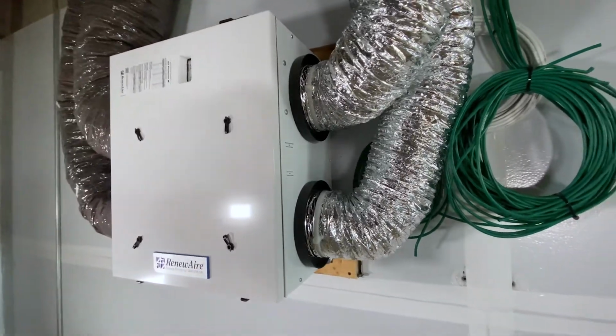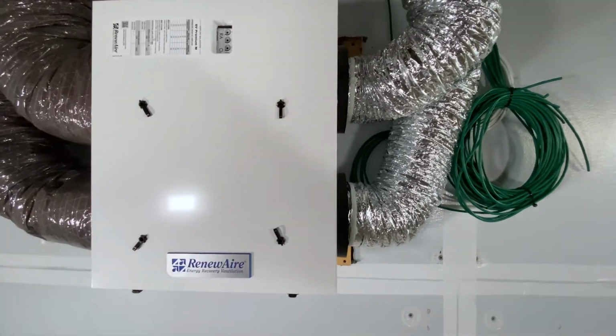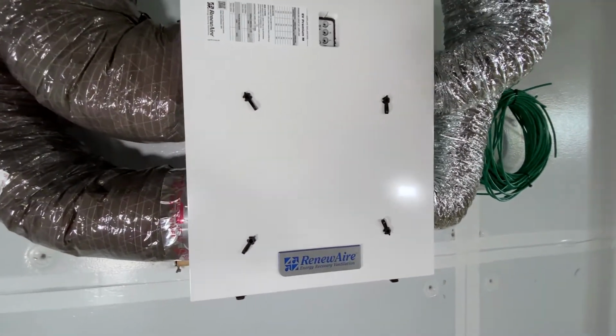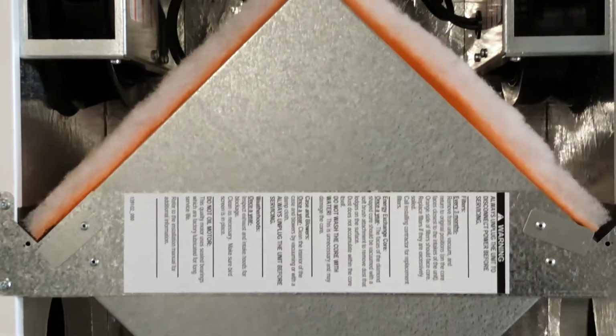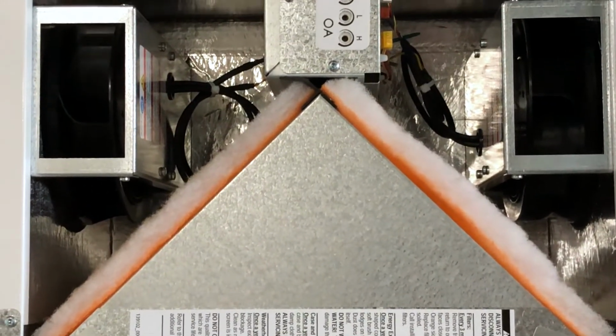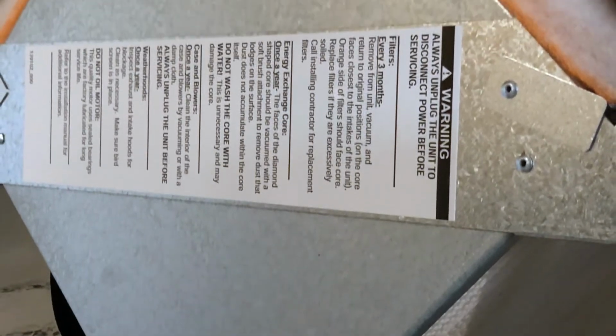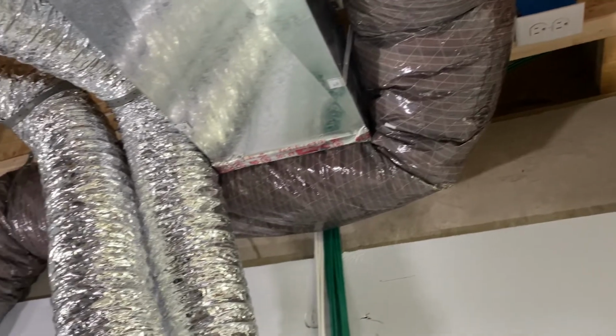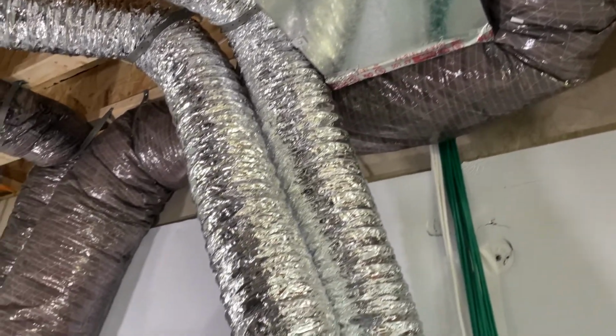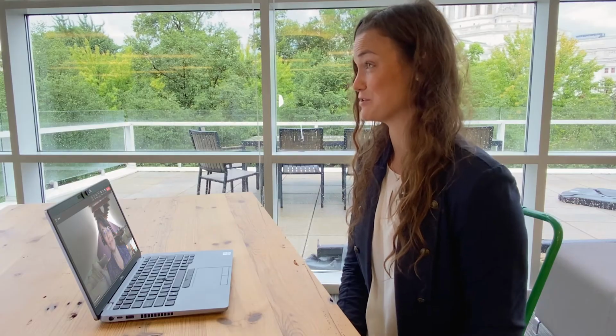Yes, definitely. Any ventilation system needs to be commissioned, which just means that it's doing what it's supposed to do. The installer needs to make sure the heat pump and ventilator are working together, and they're also responsible for setting up the controls. Since you're participating in an efficiency program, you have a building performance consultant, and they may measure and adjust the airflow of the ventilation system. This is an important step, so anyone that doesn't have a building performance consultant should make sure the installer or manufacturer measures and adjusts the airflow. Great. We do have that, which is great.